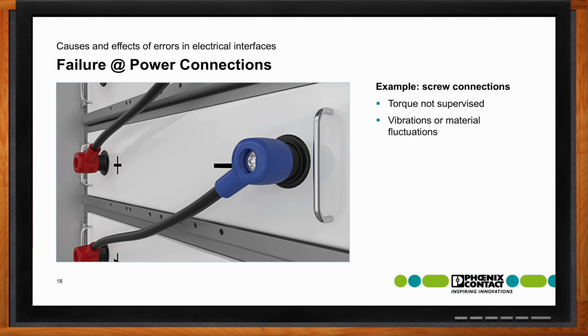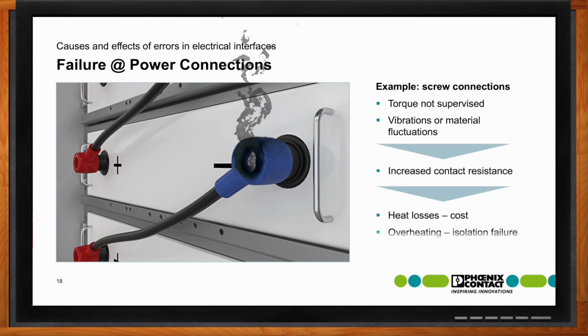Nowadays, in many cases, power connections are realized by screws. And if you do not supervise the torque of the screws properly, or if there are vibrations or material fluctuations that loosen the screws, the contact resistance will increase. This results in heat losses in the best case. In the worst case, in really strong overheating and fire events, which would destroy the energy storage system.